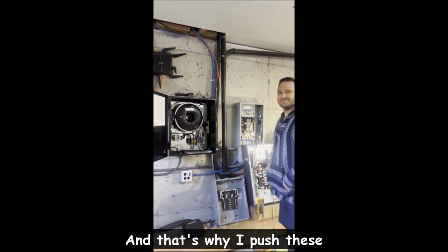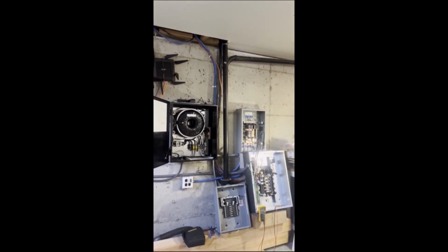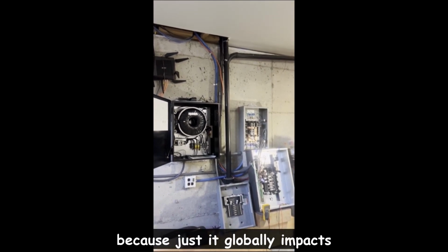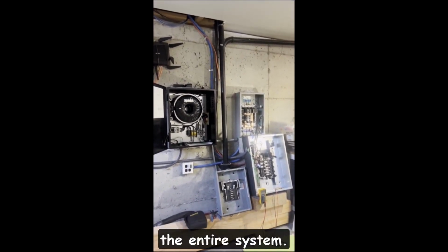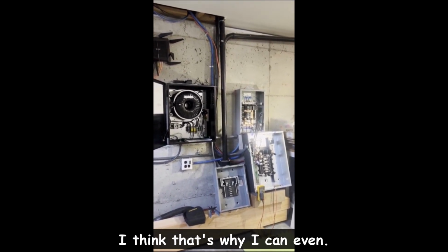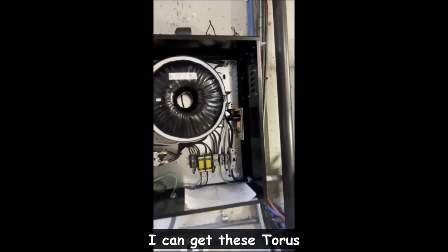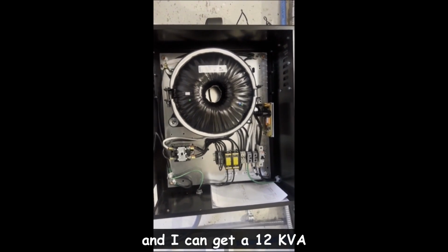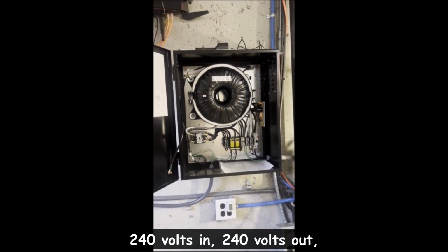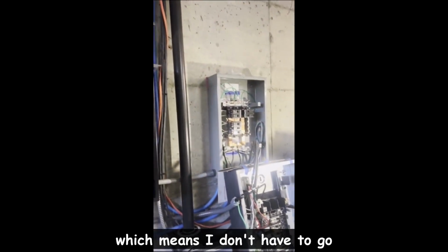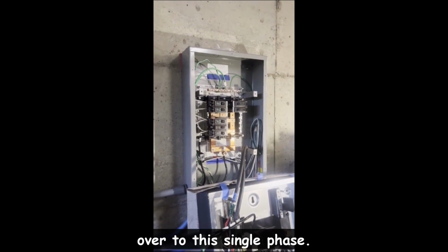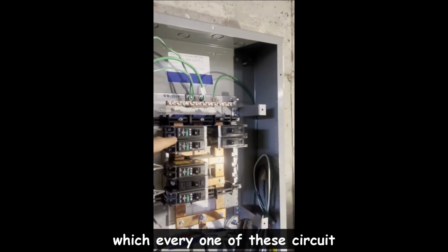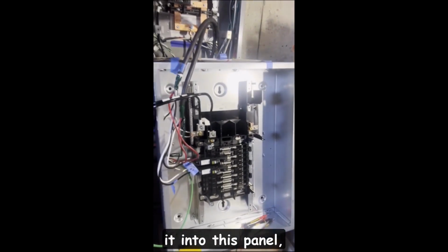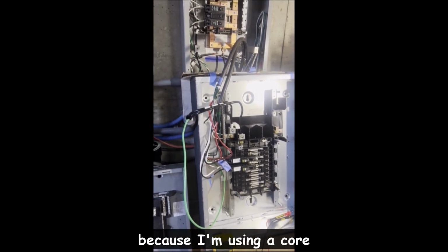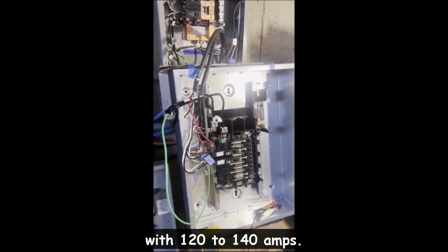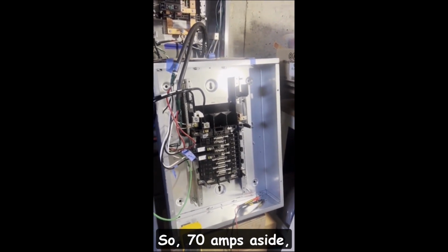That's why I push these large single output cores if you can, because it globally impacts the entire system. I can even get these now, a 12 kVA and a 14 kVA high output core, 240 volt in, 240 volt out, so I don't have to go over to the single phase setup at a $5,400 base price where every circuit breaker is $350. I can drive it into this panel, which is 240 volt rated, using a core that's 240 in, 240 out, with 120 to 140 amps, so 70 amps a side.